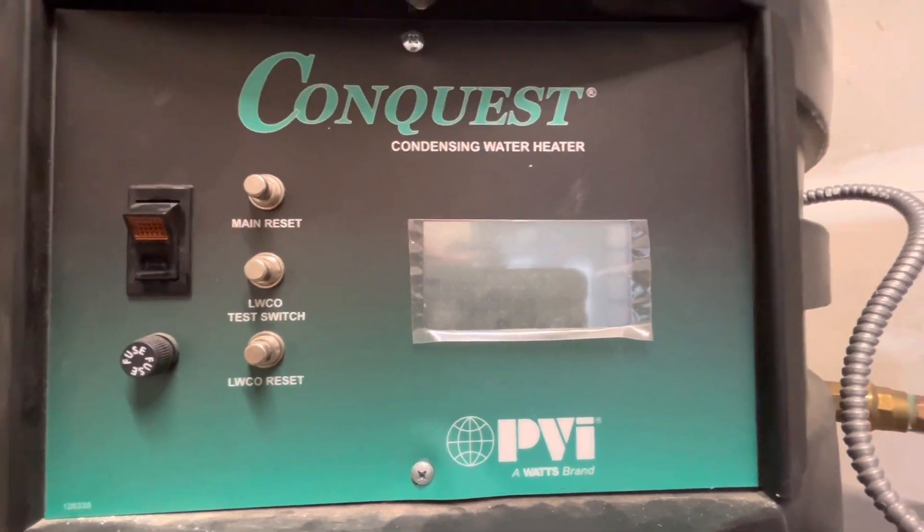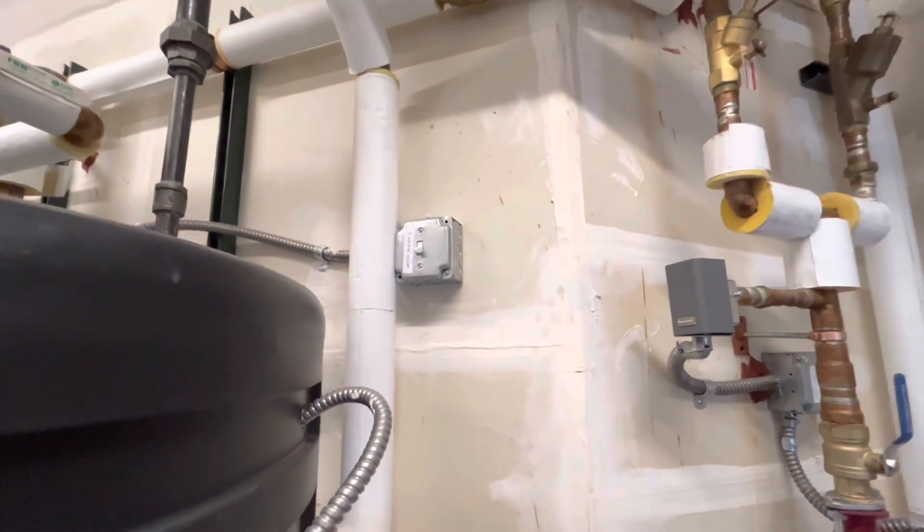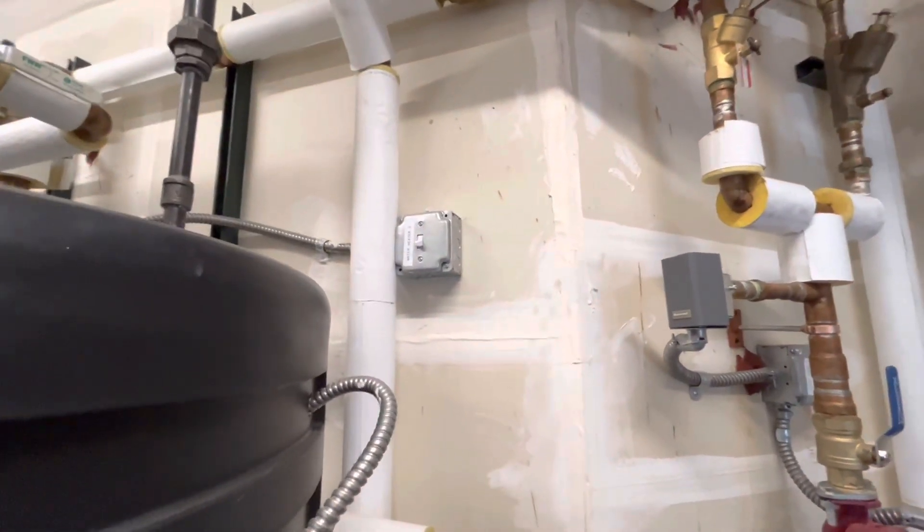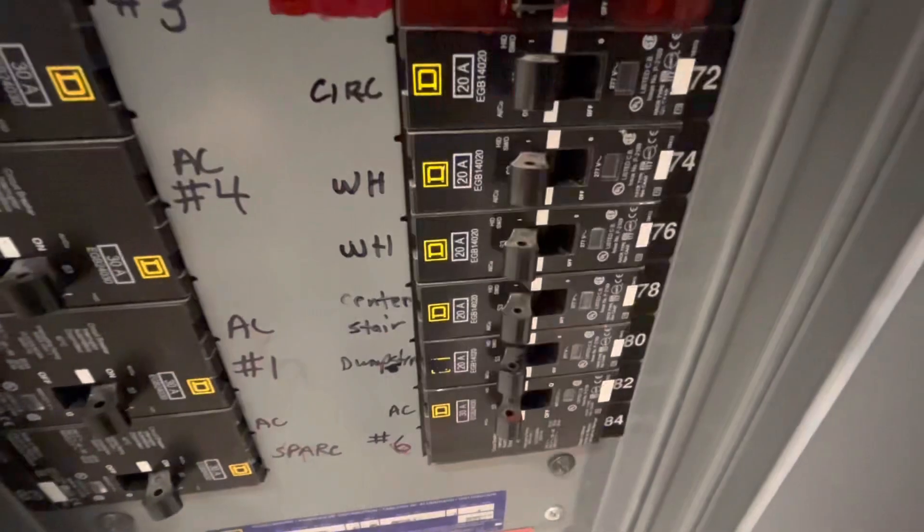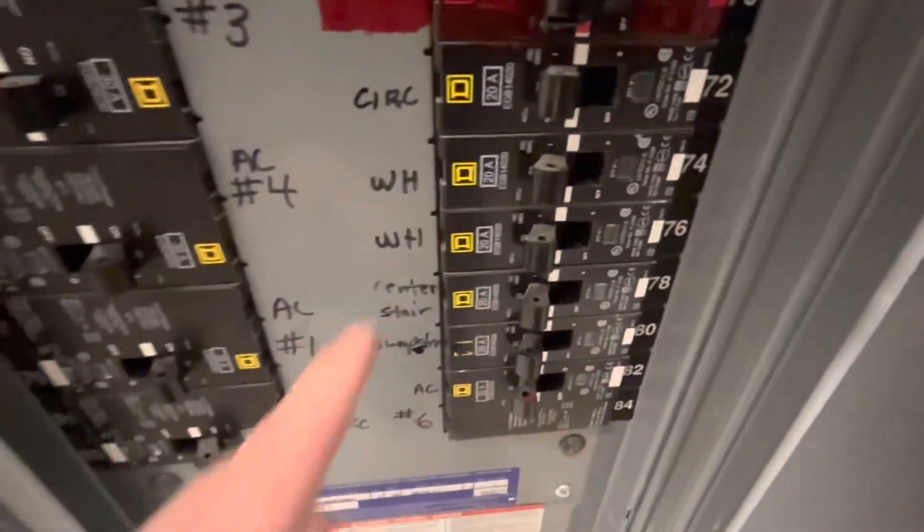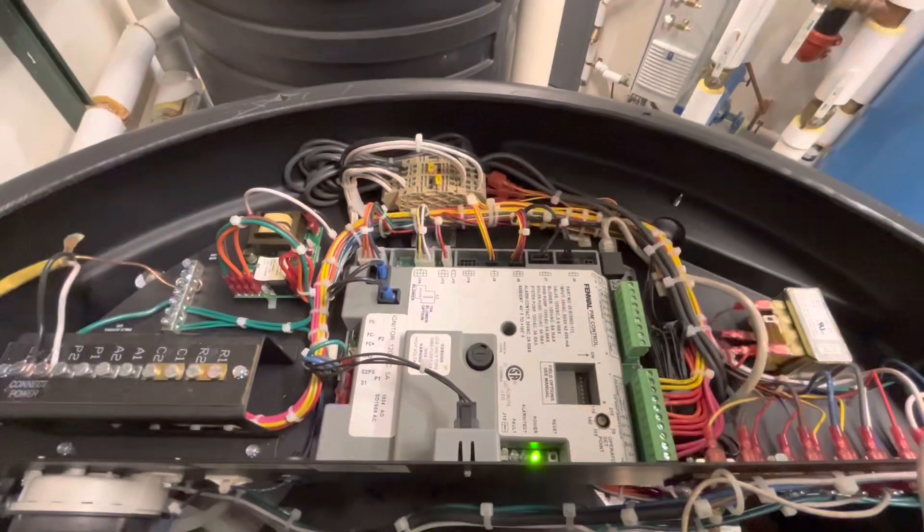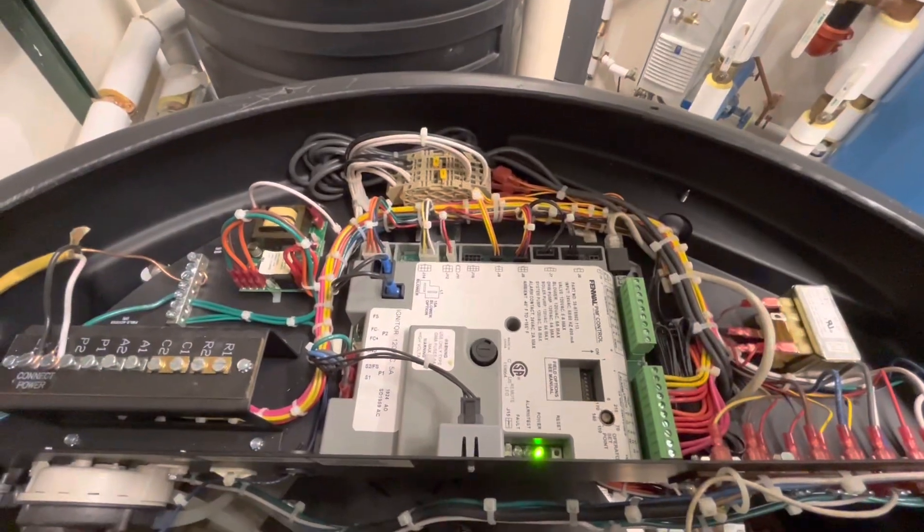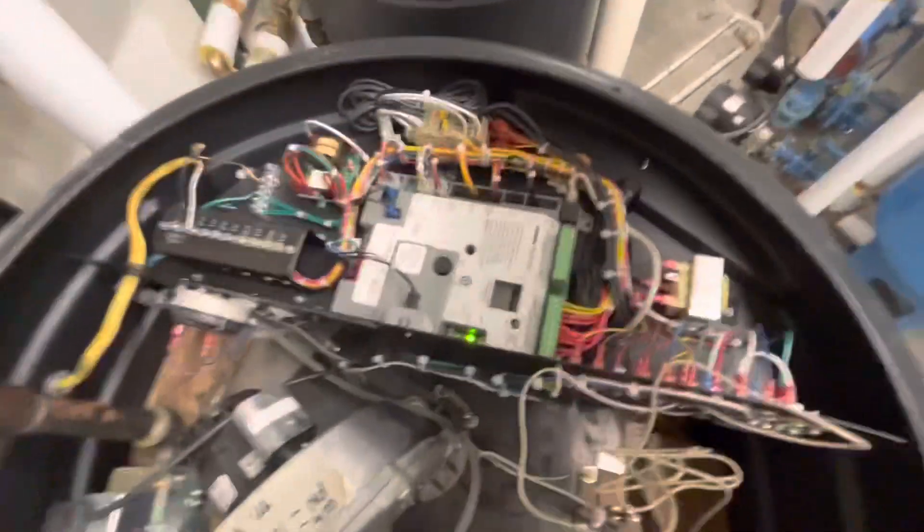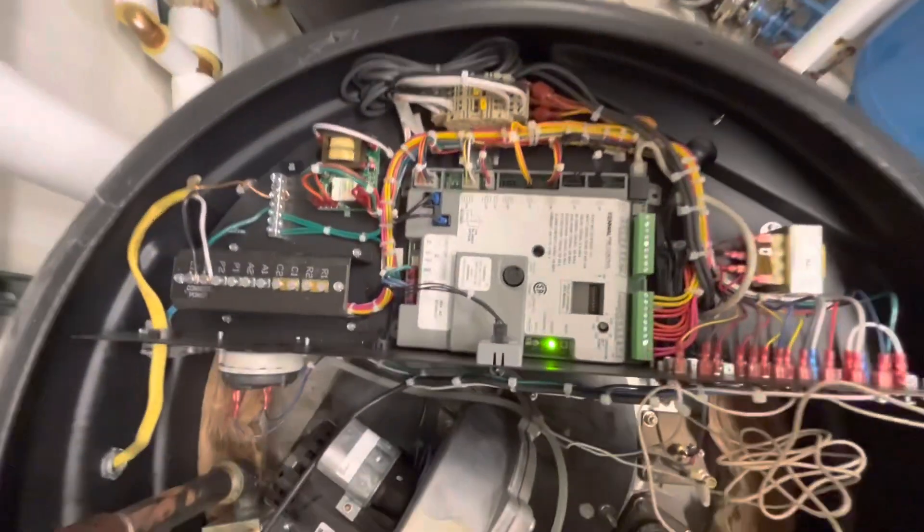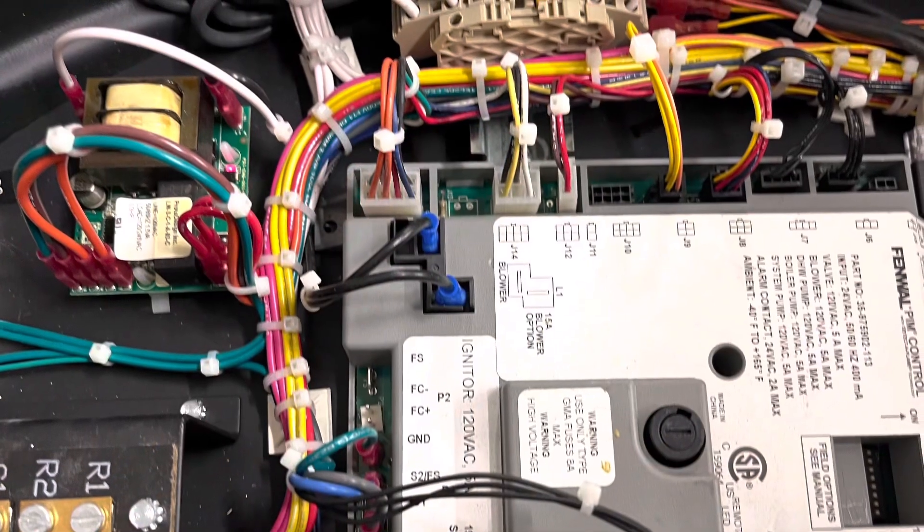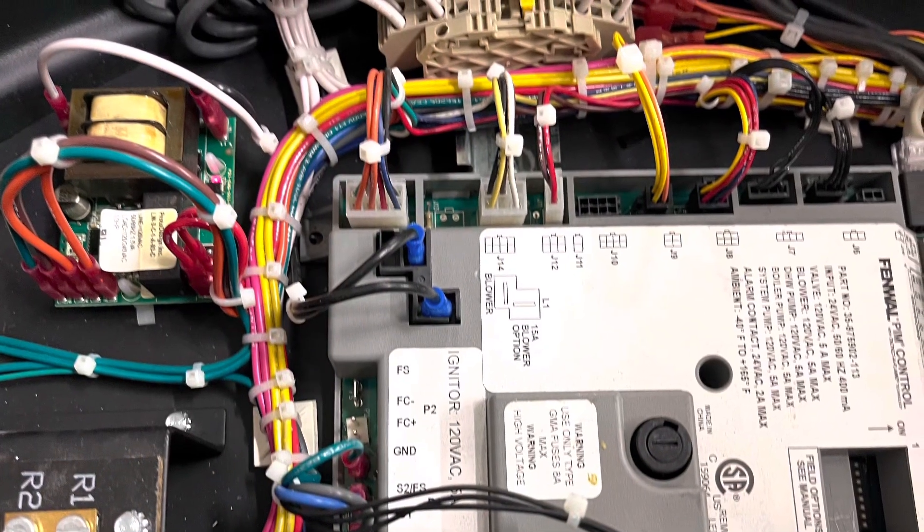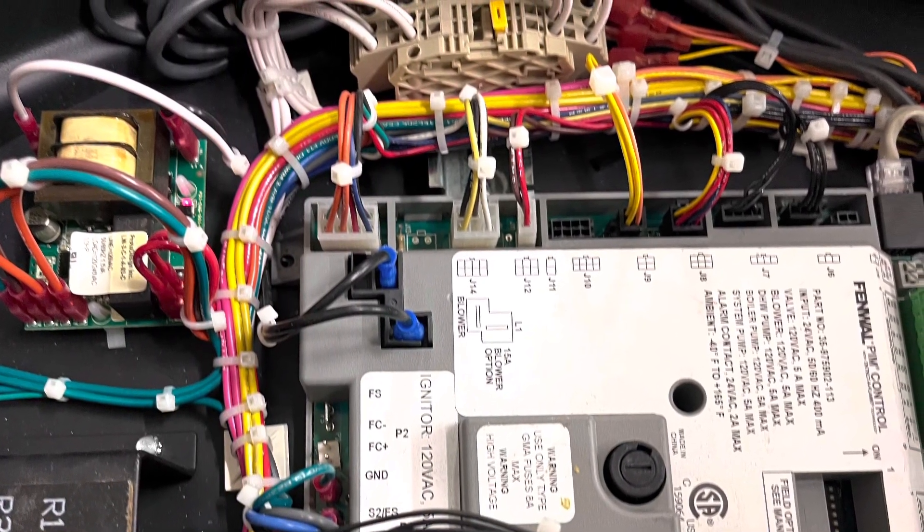Also turn it off with the breaker panel. With the power off, we can now start to diagnose the problem. We have two of these water heaters, so what I did is I swapped this control board with the other one. Sure enough, the problem jumped to the other water heater.